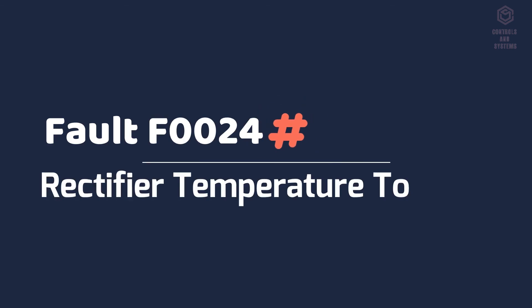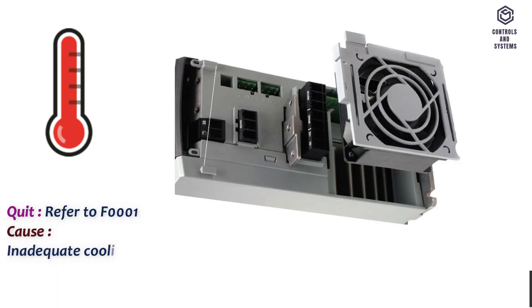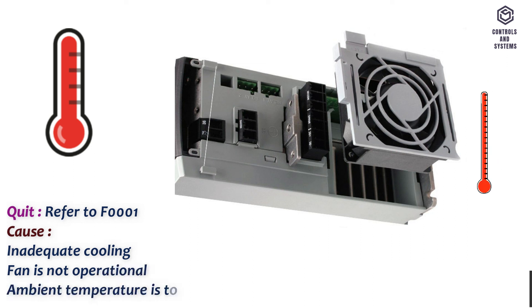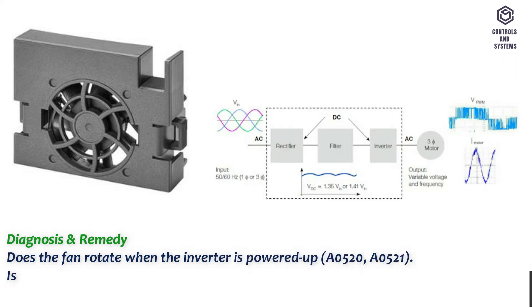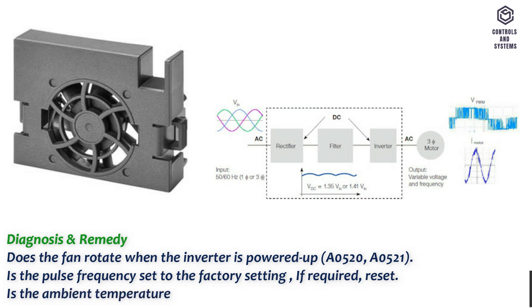Fault F0024 rectifier temperature too high. Quit: refer to F0001. Cause: inadequate cooling, fan is not operational, ambient temperature is too high. Diagnosis and remedy: Does the fan rotate when the inverter is powered up A0520, A0521? Is the pulse frequency set to the factory setting, if required reset? Is the ambient temperature within the permissible limits A0520, A0521?